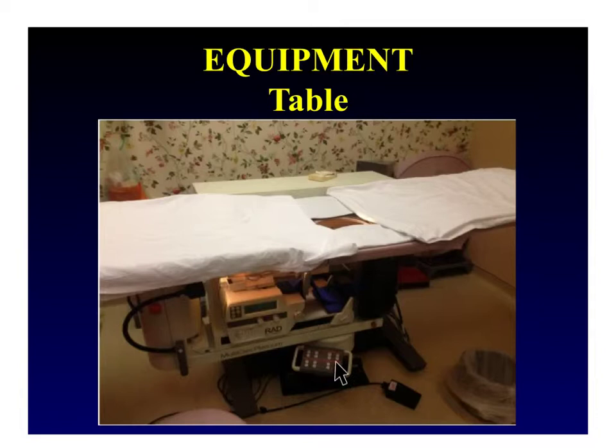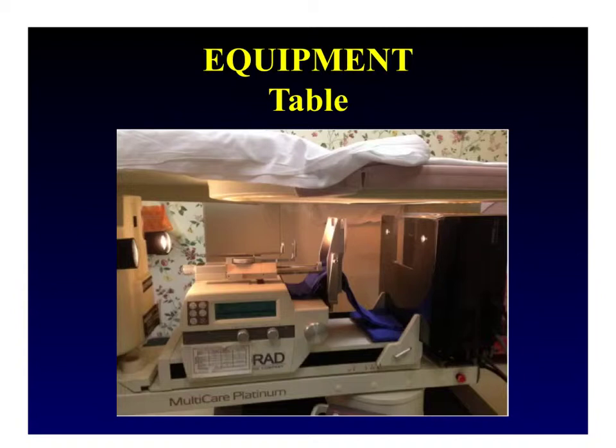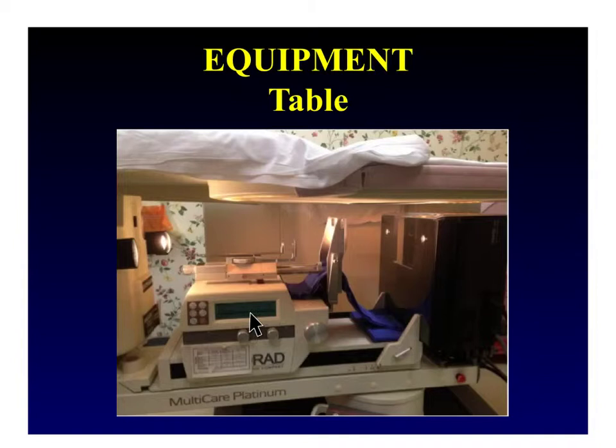The patient lays prone on the table and the breast hangs down through the hole and is being compressed between the compression paddle and the breast platform. The biopsy device rests on the stage and can be advanced in or out of the breast using the Z knob. The X and Y knobs control the biopsy device location in the X and Y coordinates. The LCD monitor shows the coordinates of the stage on the target.